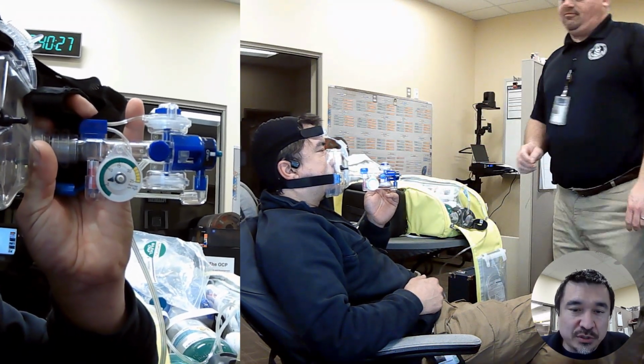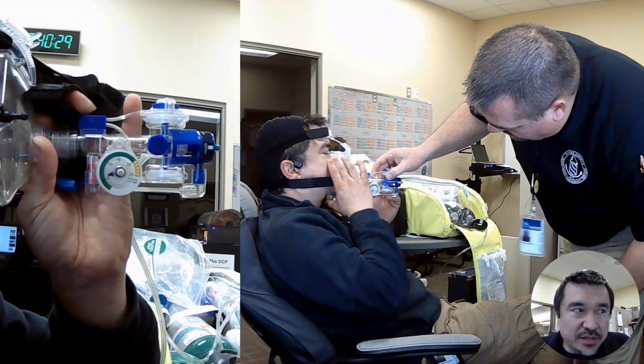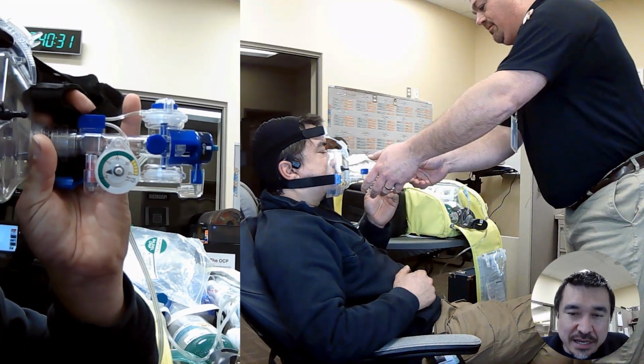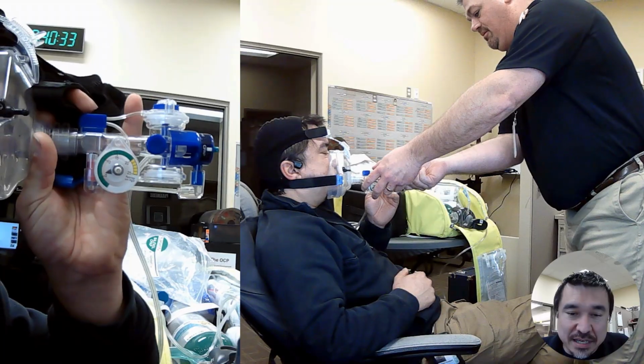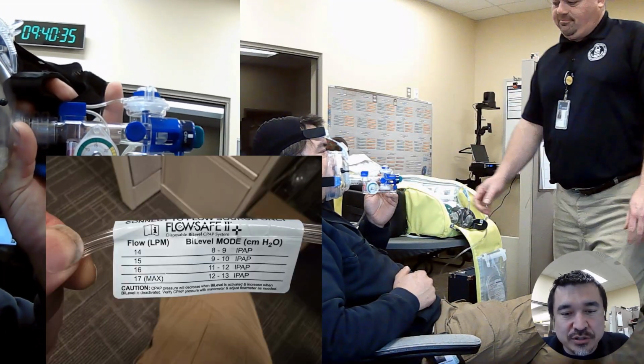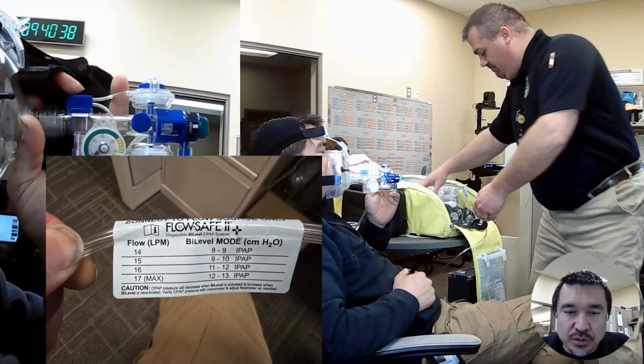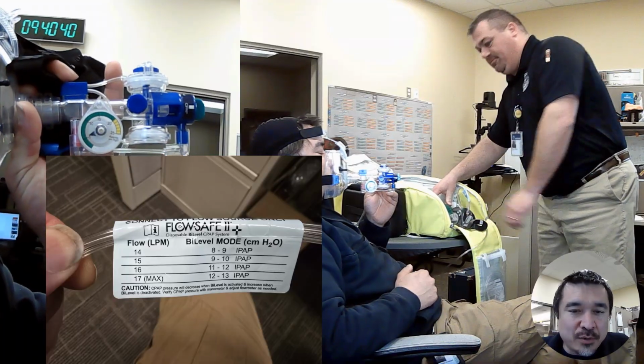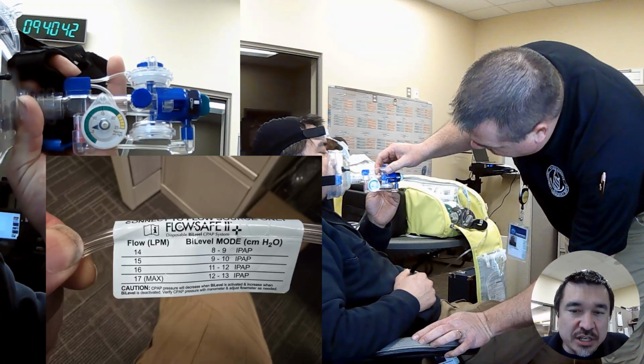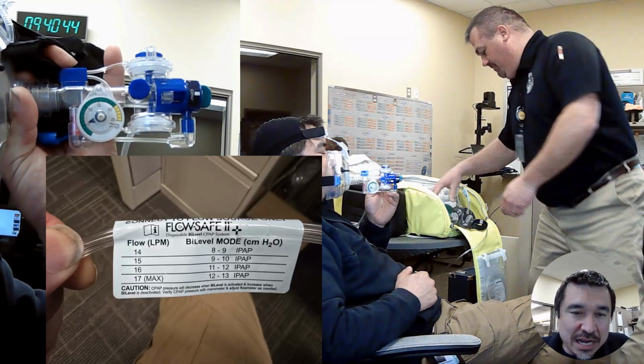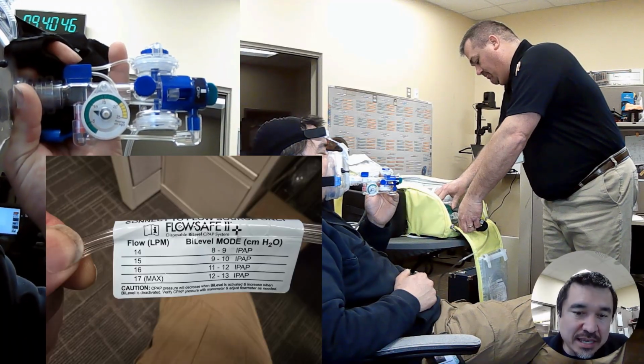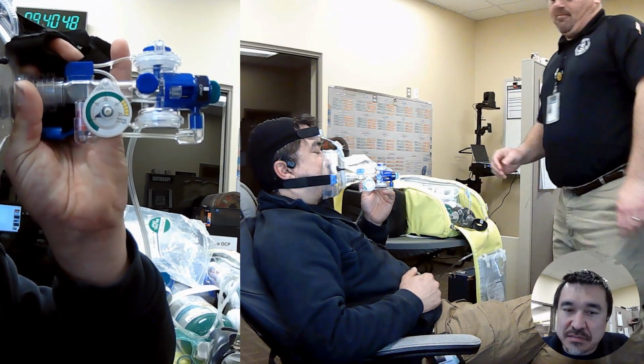Now switching to bi-level, now that's almost firefighter proof. You just flip the little blue switch on the front of the device on the oxygen tubing. On the opposite side of the blue paper is the EPAP settings. Again, this is very similar to your PEEP. So you're going to verify the EPAP on exhalation. You're going to adjust your IPAP with the little blue knob on the side of the device, or in this case on top. And that's it.